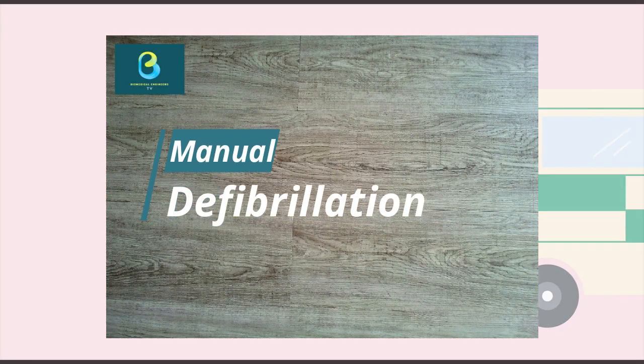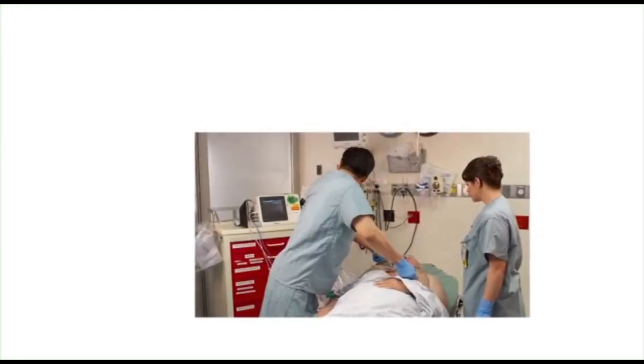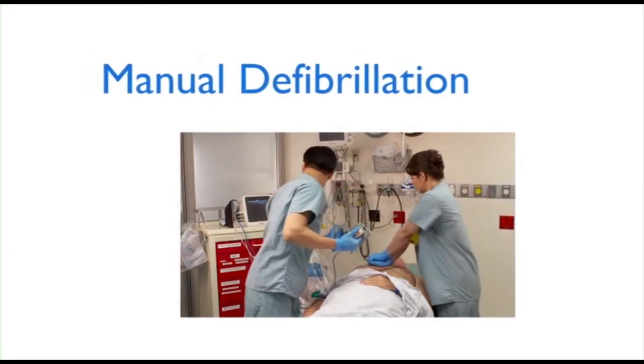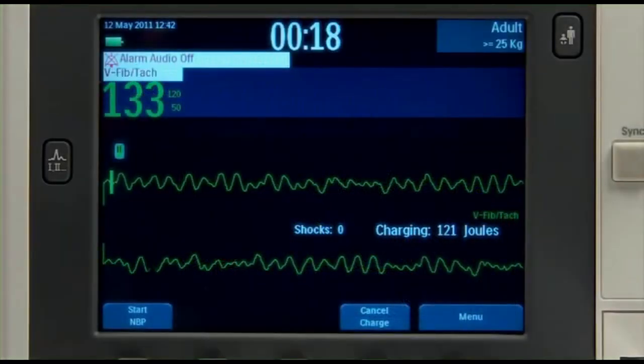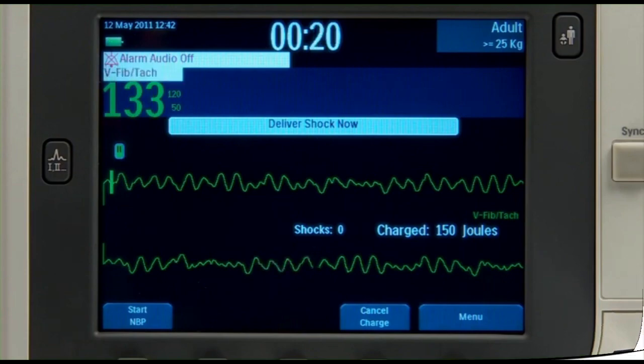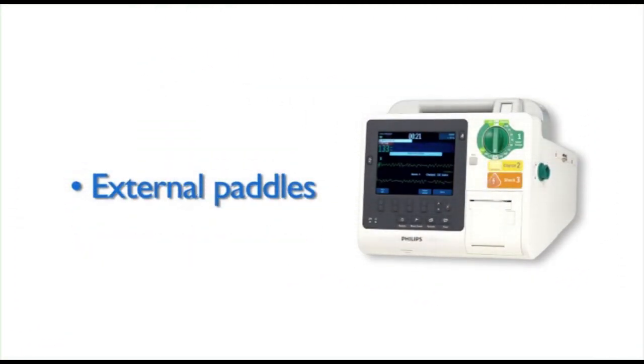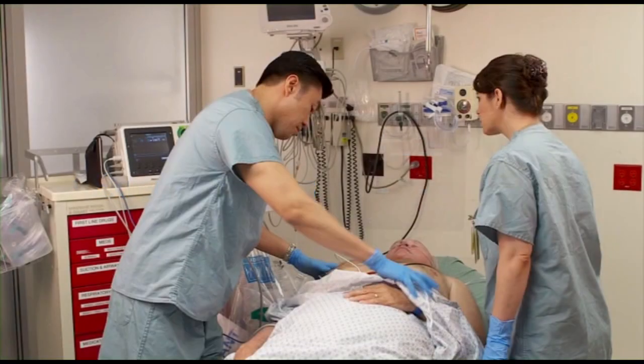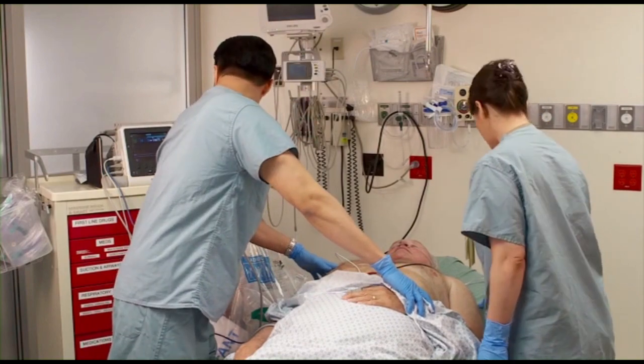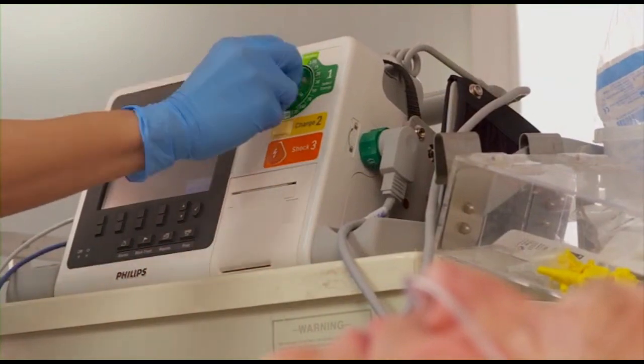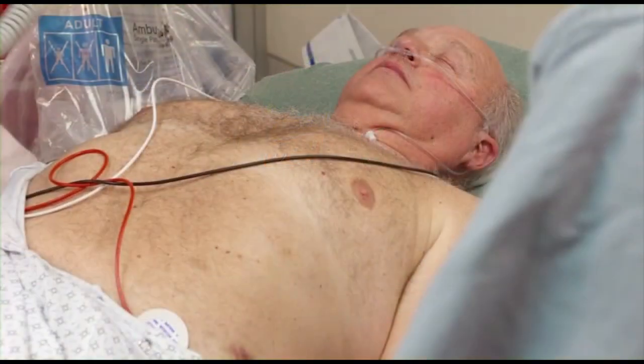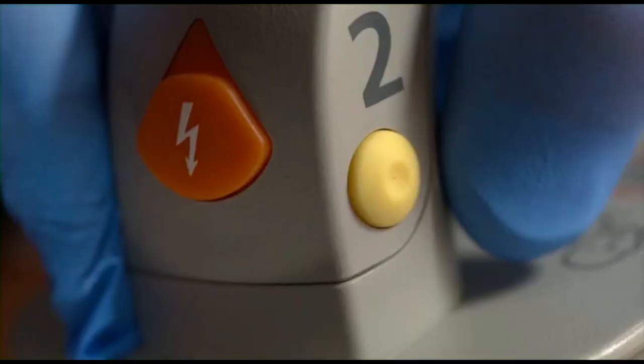Let's begin with manual defibrillation. Manual external defibrillators require the expertise of a healthcare professional. They are used in conjunction with an electrocardiogram, which can be separate or built in. A healthcare provider first diagnoses the cardiac rhythm and then manually determines the voltage and timing for the electrical shock. These units are primarily found in hospitals and on some ambulances.